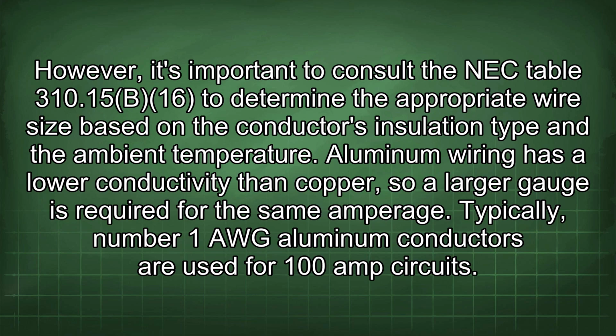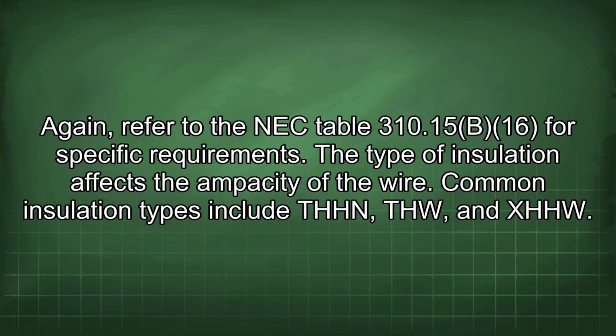Aluminum wiring has a lower conductivity than copper, so a larger gauge is required for the same amperage. Typically, number 1 AWG aluminum conductors are used for 100 amp circuits. Again, refer to the NEC table 310.15(B)(16) for specific requirements. The type of insulation affects the ampacity of the wire.